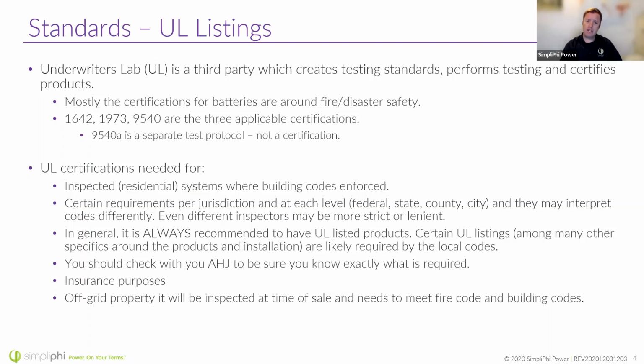So UL certifications are great to prove we're safe, but it's also necessary more recently, as a lot of jurisdictions, AHJs, and inspectors are starting to ask for these UL listings at the time of inspection. The last thing you want is to be on site the day your inspector starts asking about these UL listings and not have them. Of course, always check with them beforehand to know what's required.